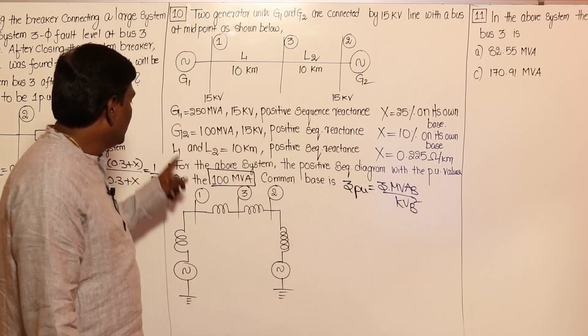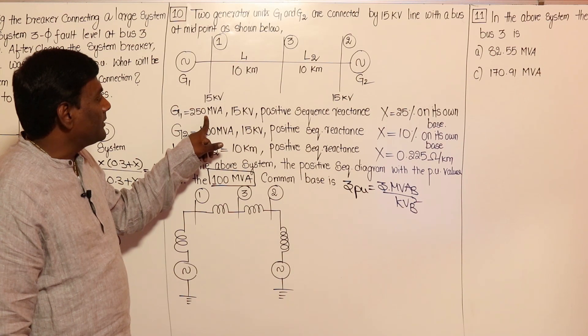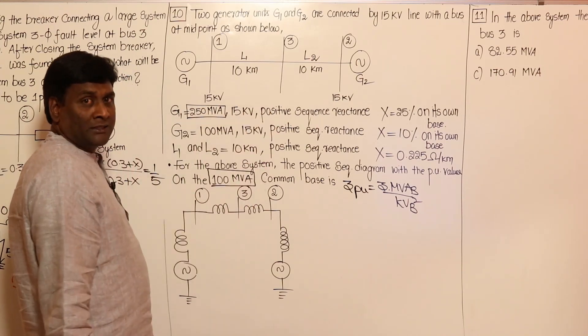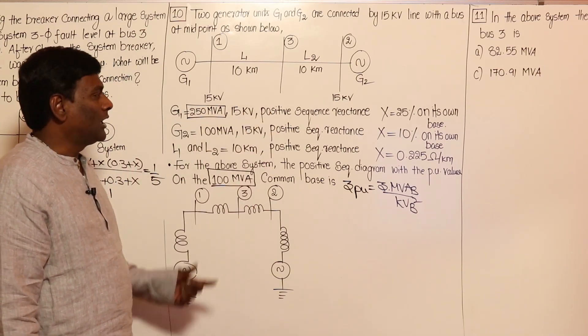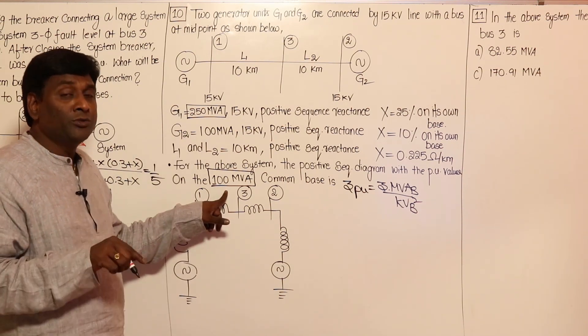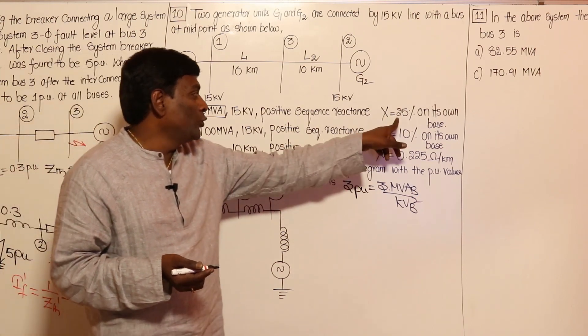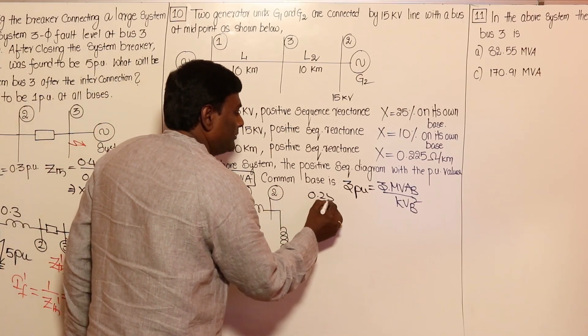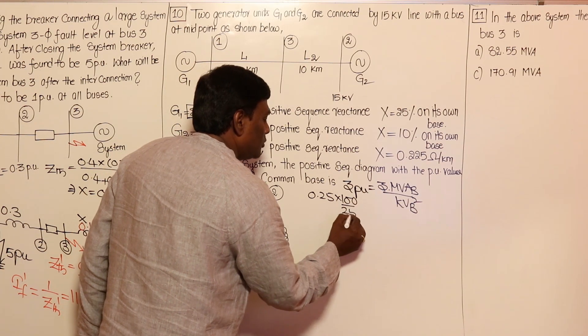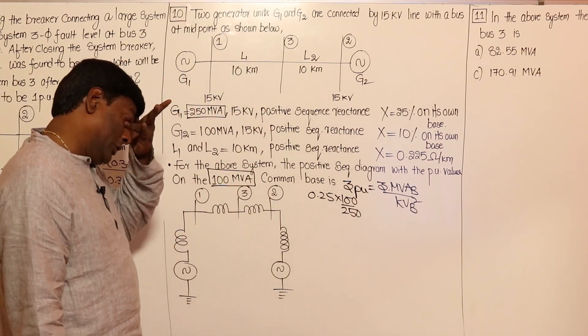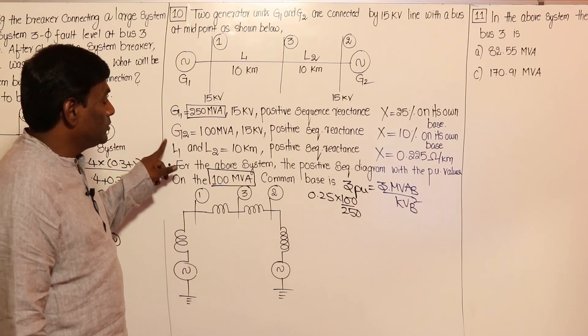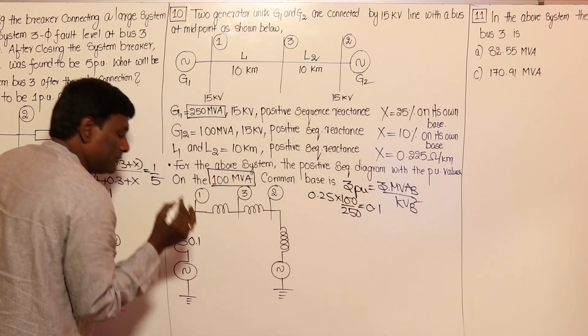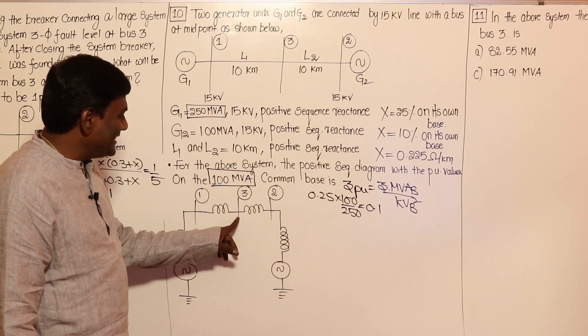Per-unit impedance is directly proportional to MVA base. For G1 at 250 MVA, reactance is 0.25 per unit; converting to 100 MVA base: 0.25 × (100/250) = 0.1 per unit. Similarly G2 is already on 100 MVA base so remains 0.1 per unit.